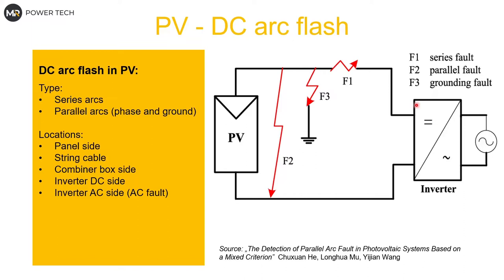For DC arc flash in a PV system, looking at the connection between the inverter and PV panels or strings, you can create a few arc types. One is a series fault arc on the same conductor. Another is a parallel fault arc — for example to ground, which would be a grounding fault. You can also create an arc between two phases. In practice it is very hard to detect a series fault, and because of the nature of PV systems with very low fault current, parallel faults are also hard to detect.